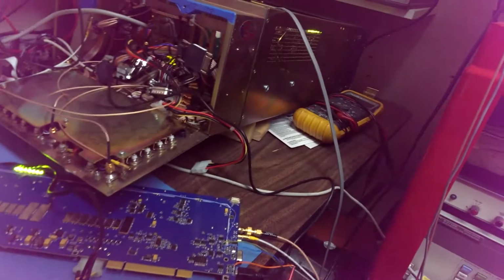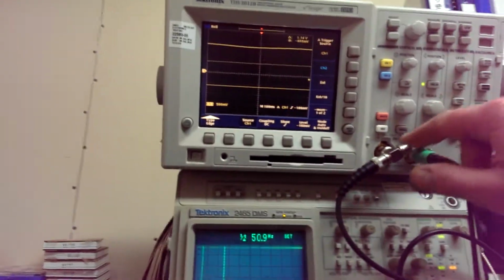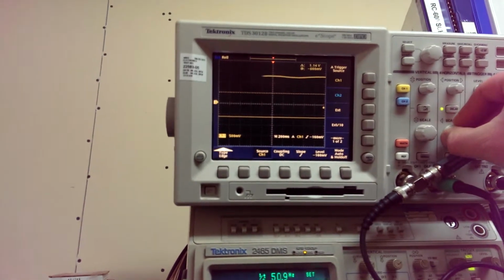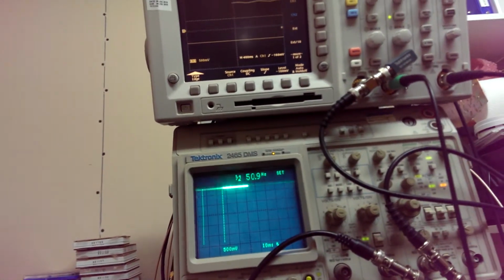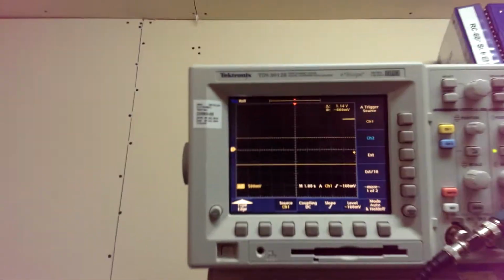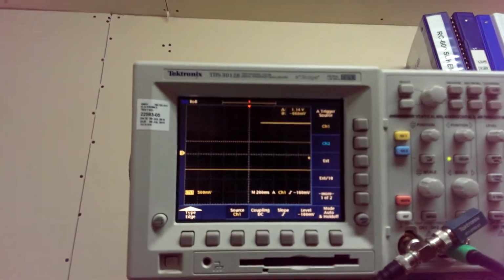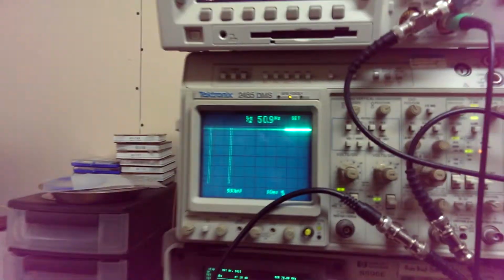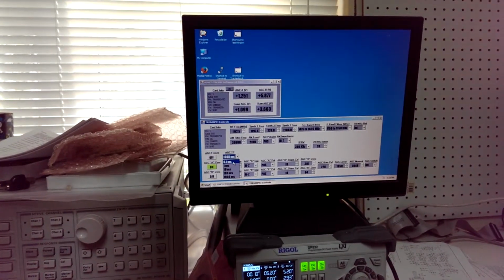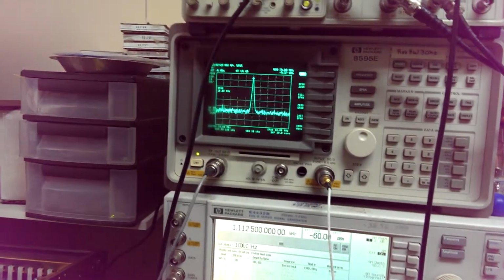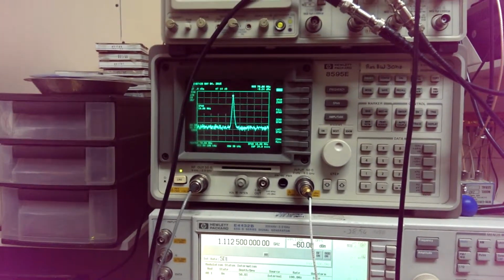Now on the same deal, if we go from AM and we look at the AGC output while we're in AM, you will note, and let me bring that rate up to like 100 hertz here, you will notice no response at all on the AGC, because 100 hertz is well within the AGC response rate. But should we go to a fast AGC, like 0.1 milliseconds, you'll note it. Oh, that's right, I'm on the internal.